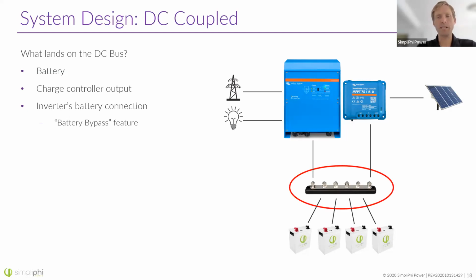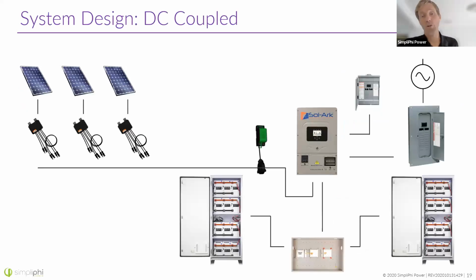So I'm just pointing out the DC bus there. This is kind of a bad example of a bus, but there are lots of different buses that you can buy. Make sure it's rated to the maximum output of your batteries or whatever your limiting device is, and your fuses. So what we're showing you here is a DC coupled design. You see the solar panels on the left, those are rapid shutdown devices there with the panels. Those are required for roof mount arrays. There's the green thing in the middle of the screen there. That's a signal transmitter for those.